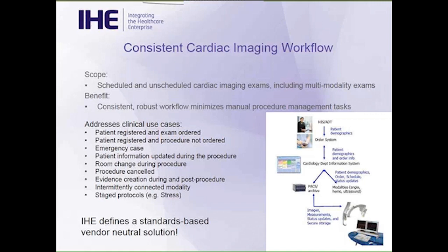And in doing so, we've been leveraging base interoperability standards, including HL7 for patient registration, for order placing and order scheduling, and also DICOM for maintaining consistency of patient demographic and ordering information via modality worklists, and also for conveying status from modality to the different other systems involved about the procedure, exam, and acquisition.